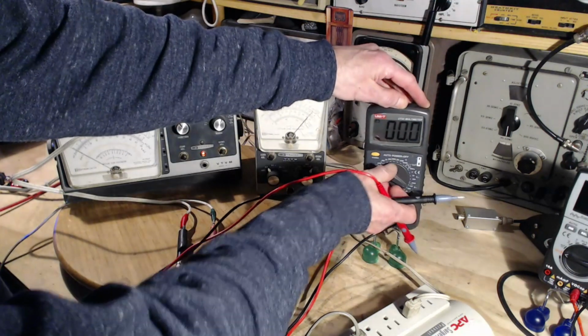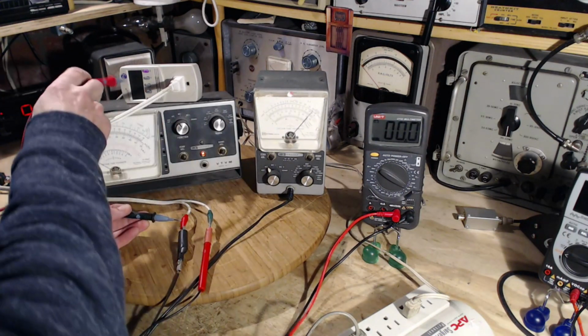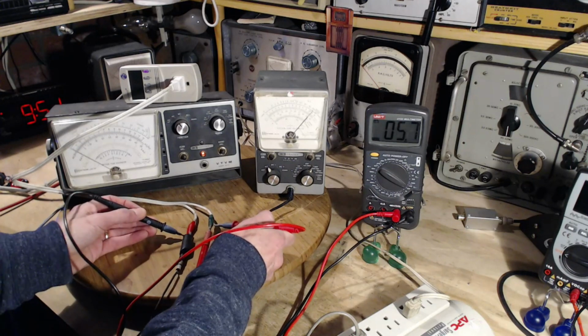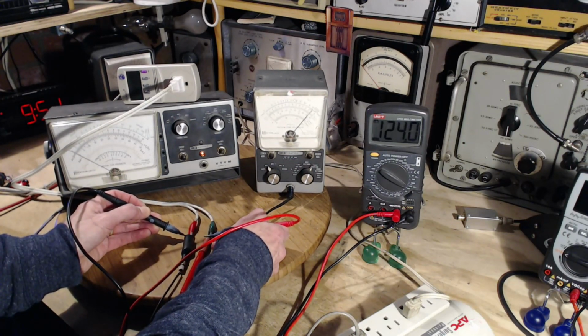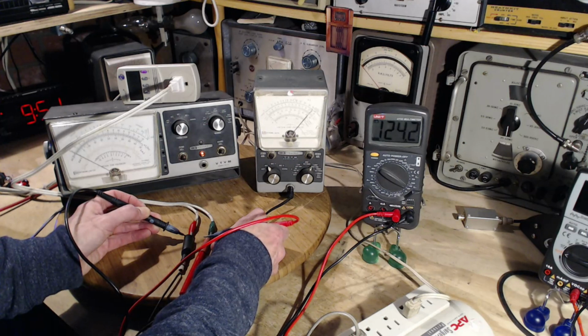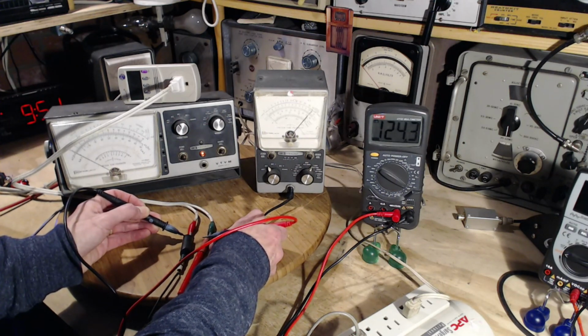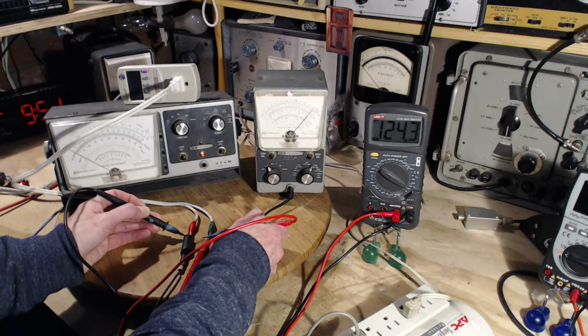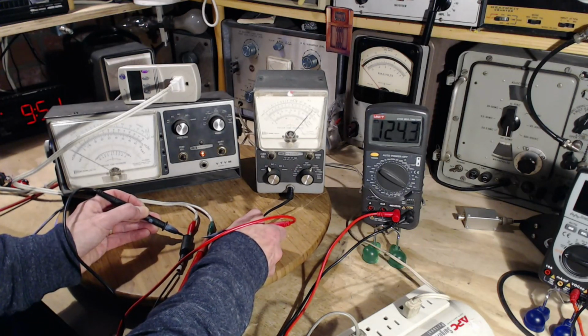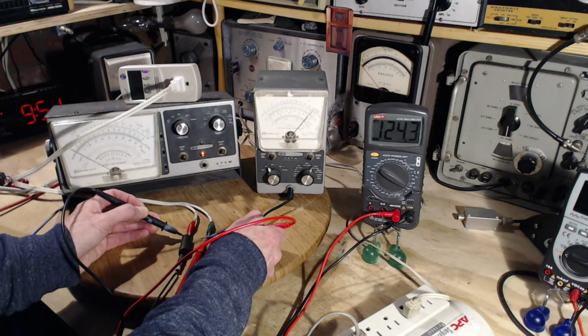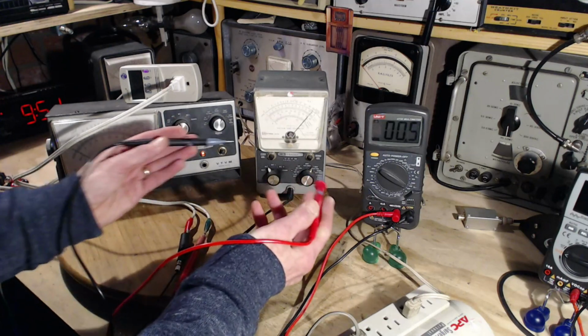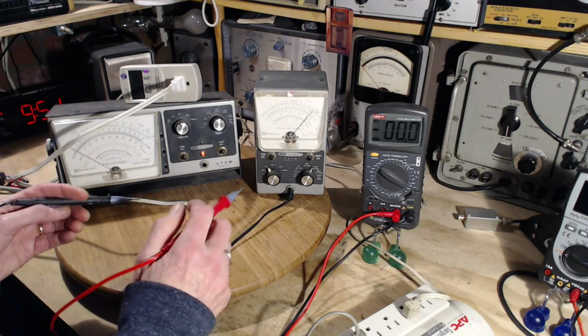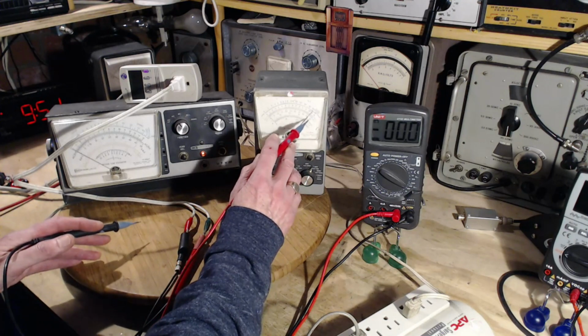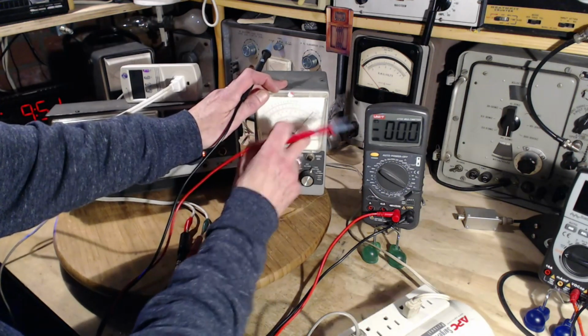Okay, and we're going to read the voltage here and compare it to everything, including this. 123.9 is what it says on there. It's really darn close, isn't it? Okay, it still says 123. It's bopping around between 0.7 and 0.9. So it's basically 123.9, 124.3. And both meters could be correct? No. I'm reading a higher voltage on this meter. So one of these is not 100%. In the meantime, this one is still reading 139.